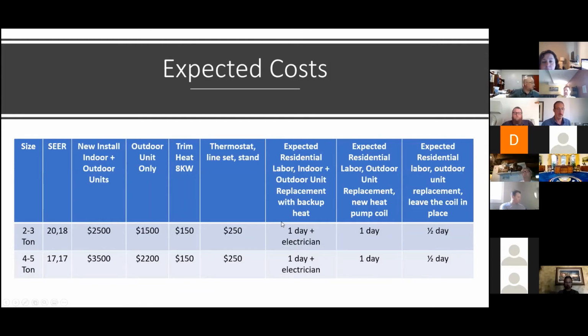So if I'm going to rip out the furnace and put in a new heat pump with trim heat and a new outdoor unit, that's probably one day, but you will need an electrician to power up the indoor unit. If we're just going to replace the outdoor unit and the heat pump coil and leave the furnace in place, I've got a day here, but Jeff has suggested to me a few times that a good tech should be able to do it in half a day, because there's a lot of time waiting to pull the refrigerant out and then put it back in, and in that time you could probably change out the coil and run a new heat pump thermostat.